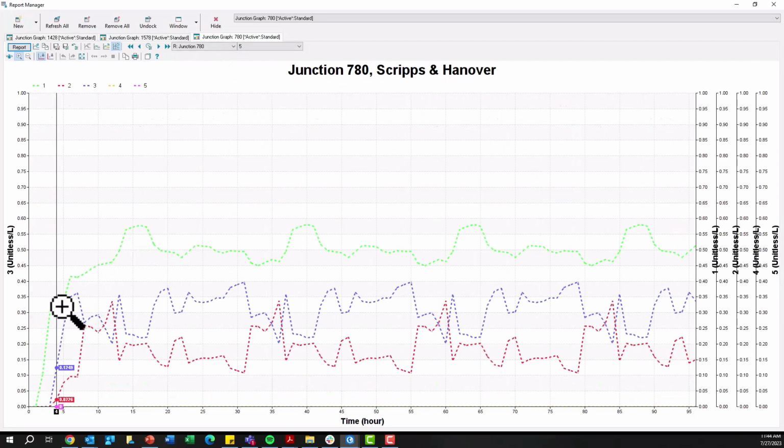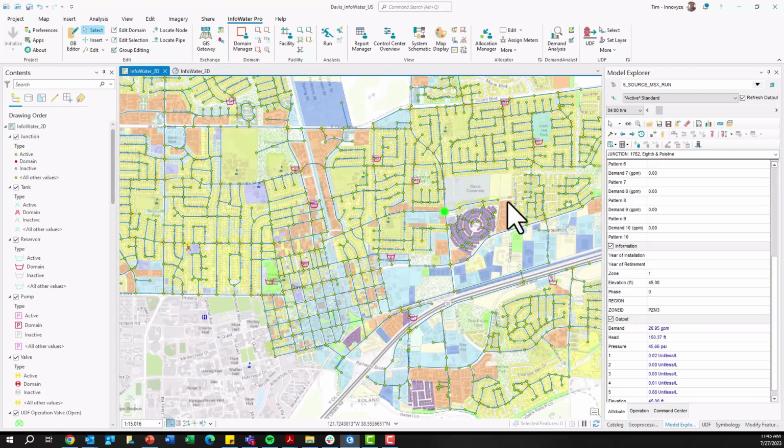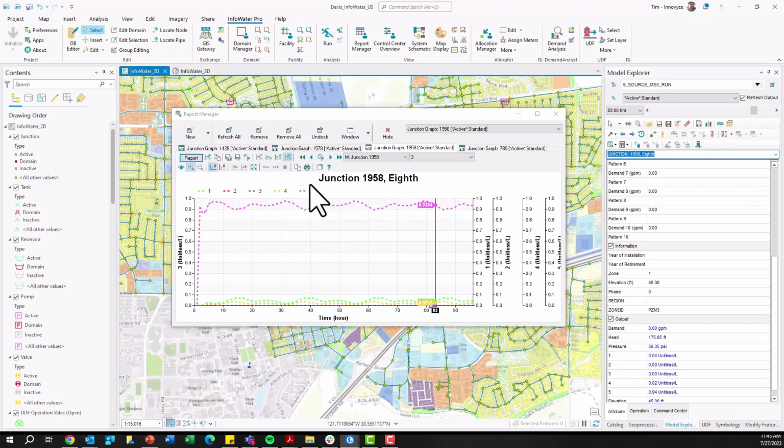So I can see, at this particular hour, we've got 32%, 12%, and fractions beneath that in terms of water quality there. You're going to want to go out to a later run, a later point within your model, so 4 hours probably won't have everything add up to 100%. So if you go out to a later hour here, I'm going to see that those values more likely add up to 100% flow there, 100% from my different sources.